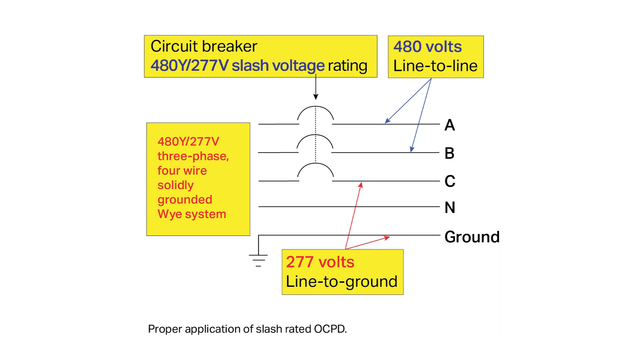The proper slash rated circuit breaker application is such that the line to ground voltage does not exceed the device's lower voltage rating, and the line-to-line voltage between any two conductors does not exceed the device's higher voltage rating. Understanding the higher and lower ratings is important, as slash-rated devices' misapplication can result in it being applied outside its voltage rating, with dire consequences should the device be called upon to interrupt overcurrents.